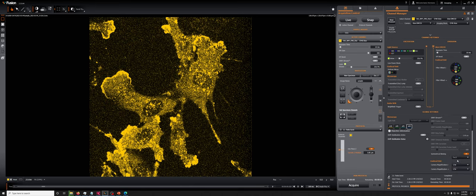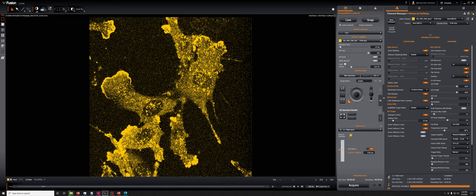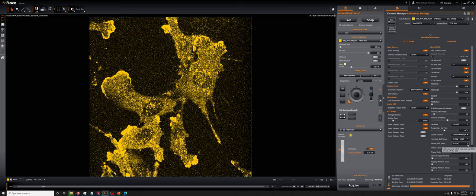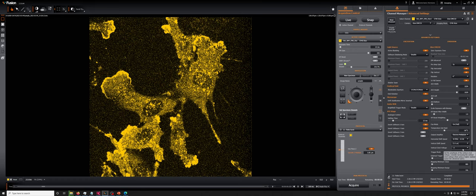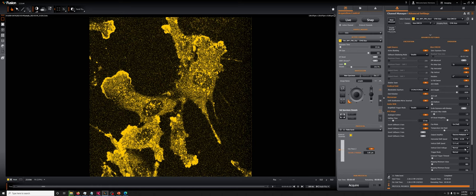Let me show you one final control element, which is in the advanced mode, something called the vertical shift speed and vertical clock voltage. And actually this is not set currently to the default position because I forgot it at a position where it leads to higher speeds. The default position for these two parameters are a vertical shift speed of 2.2 and a vertical clock voltage that's normal. But if you reduce these to 0.6 and increase the vertical clock voltage to plus one, you can gain some speed. So here we're going in the opposite direction. I took them back to normal. And so we expect that this will take longer.